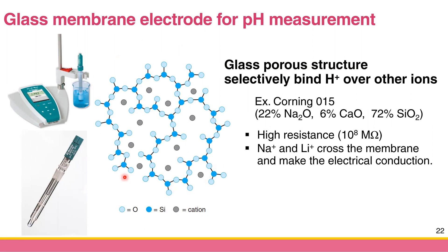The bluish thing in the diagram is the silicon — SiO2. General glass is not going to be selective, so in order to make the glass membrane specific for pH or proton measurement, they fine-tune the manufacturing process and add chemicals. For example, Corning 015 is the glass membrane that selectively responds to protons, and it has 22% sodium oxide, 6% calcium oxide, and 72% silicon dioxide.